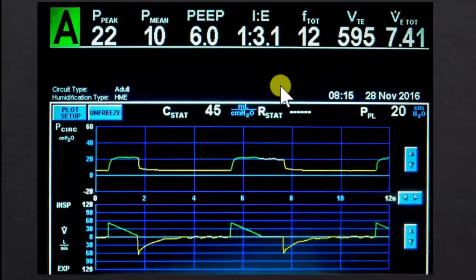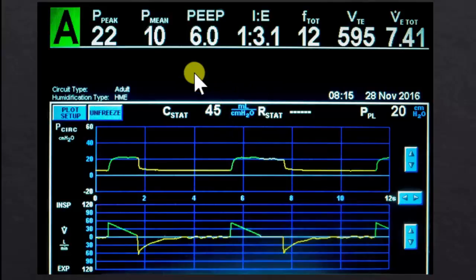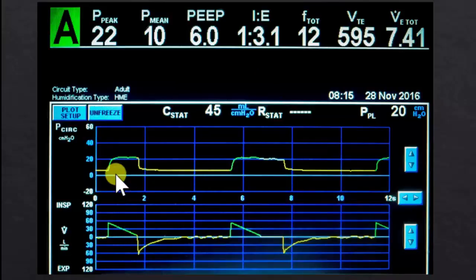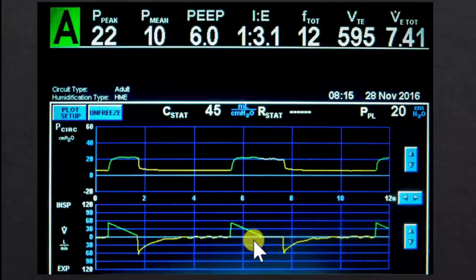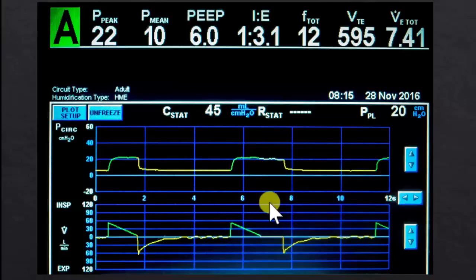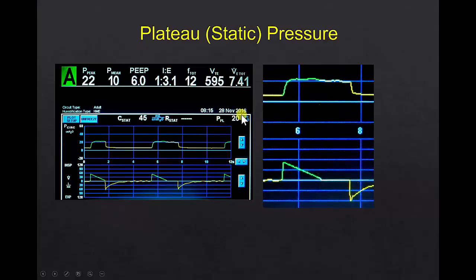We can measure compliance on a ventilator. Here's a screenshot from the 7200 Puritan Bennett ventilator showing total volumes delivered of about 600 cc's with a set flow pattern, generating a pressure curve. The peak pressure of 22 is determined by a combination of the volume and flow against the compliance and resistance. We placed an end-inspiratory hold to allow pressure going over the flow resistance to dissipate, so the only pressure remaining in the lungs is the inflation pressure needed to stretch the lungs to a total volume of 600 cc's.